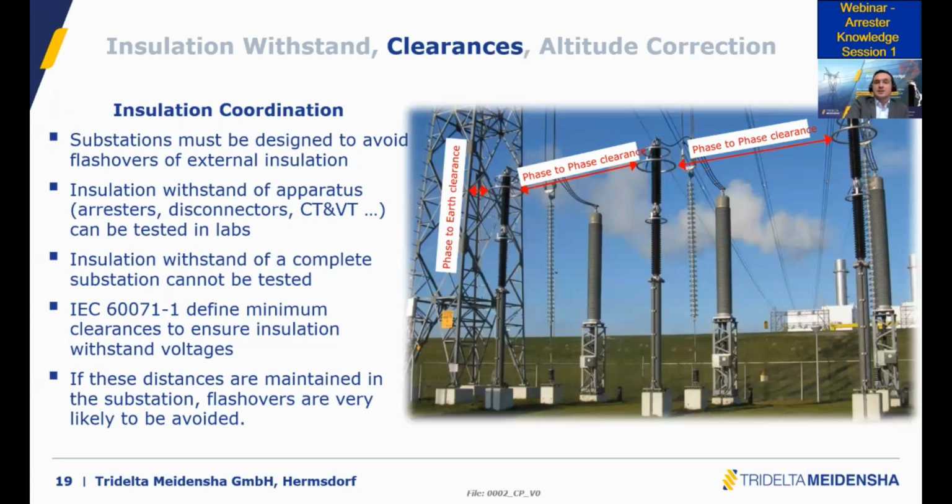Which is important for the design of the substation to avoid flashover on external insulation. So basically, the clearance, which is the arcing distance for an equipment.